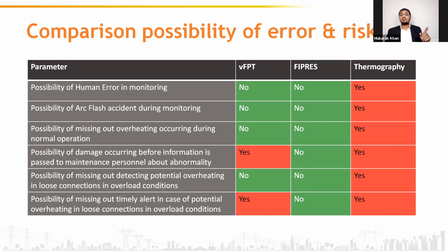Now, this is important. Possibility of damage occurring because the information about an abnormality is not passed to maintenance personnel in time. In that case, there can be damage in the presence of VFPT and thermography, but FIPRES gives a timely alert. Possibility of missing potential overheating in loose connections in overload conditions: with thermography, it is possible because you do it under normal load condition periodically at some time. But because FIPRES and VFPT are installed 24/7, they monitor the joints in all scenarios, even in overload scenarios.